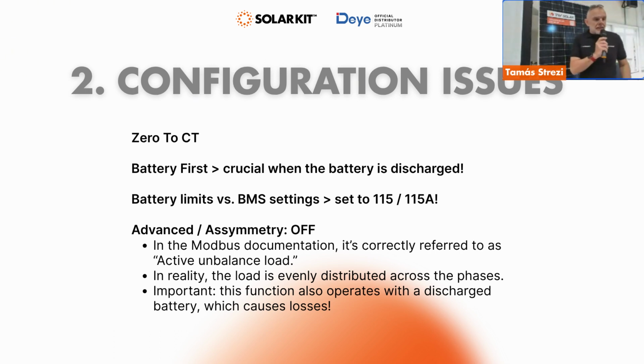My pet peeve is advanced asymmetry. This function is called asymmetry, but it's not really. I checked it up in the Modbus communication, and it's called active unbalanced load, which means that the inverter is continuously working to equalize the consumption to the meter side. So, for example, if you have a 3 kilowatt load and the battery is flat, again, we are talking about winter conditions. So if you have a 3 kilowatt load on the inverter or in your house, the Deye is working in such a way, if this option is on, that it presents this as 3 times 1 kilowatt load on each phase to the electricity grid.